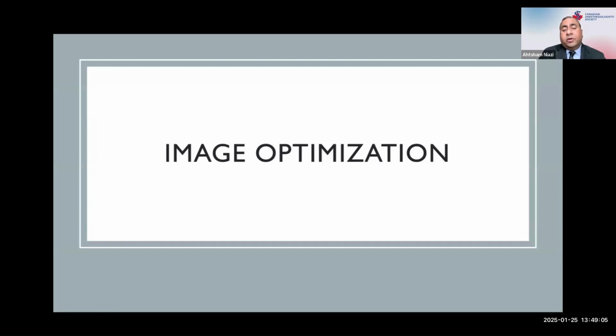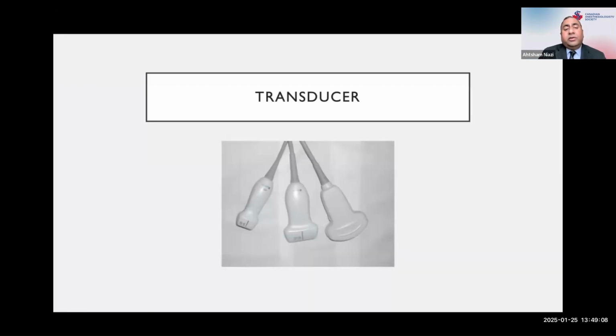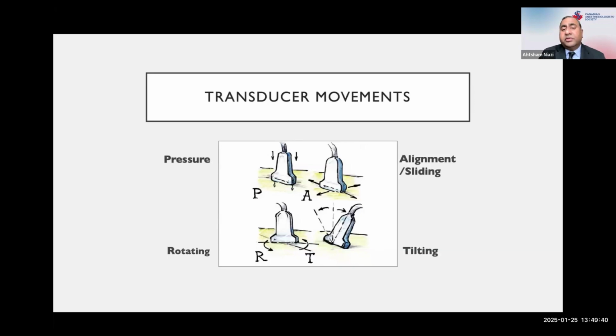The next thing is image optimization. How can you do that? First of all, the most important thing is to select the right probe. There are a number of probes on a machine. The most common probes that are used for regional anesthesia are the linear high frequency probe or the curvilinear low frequency probe. The high frequency probe is best for superficial structures as it has the best resolution up to about 4 centimeters. Low frequency probes are good for deeper structures as their resolution is best below 4 centimeters. The next thing is transducer movements.